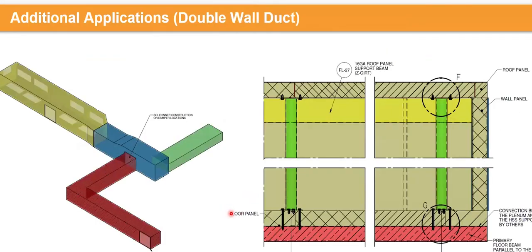I do have an example here that you could see. This is a supply duct connection. These are ductwork that they needed to run through on a roof. As you can see, after structural design, we have 8 feet of spacing between the posts that are required to ensure this meets the structural performance or integrity at 6 inches of water gauge. This is much, much wider and would provide fewer obstructions compared to what you would have using the SMACNA guidelines.